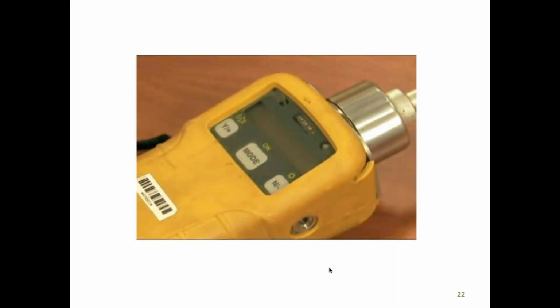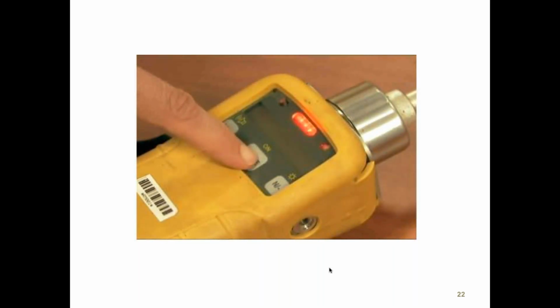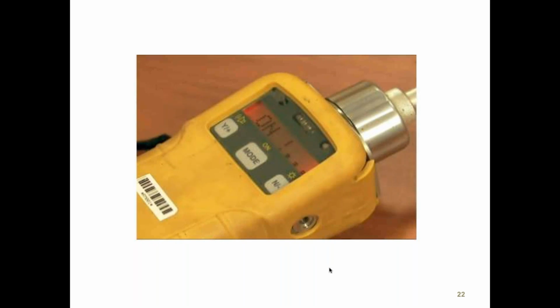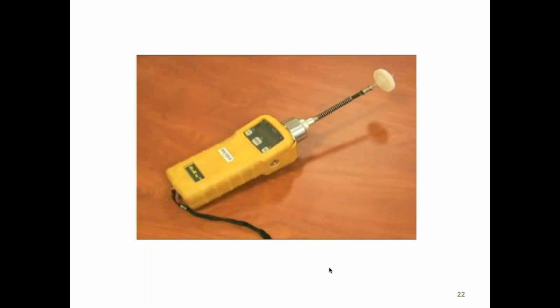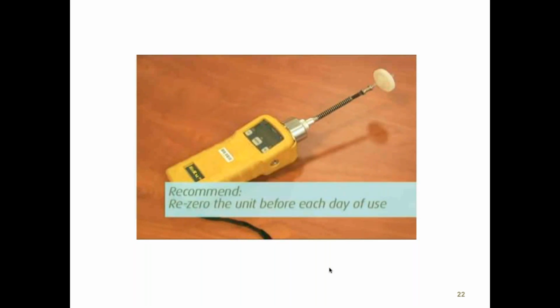One of them is for the charger, and the other one is to allow the unit to connect to a computer. Push the on button. Diagnostics checks. This will take approximately 2 minutes to complete. Once the unit has gone through the diagnostic phase, it will begin to take readings and data log results. Although Galson Laboratories zeroes the unit before it goes out, we recommend that you re-zero the unit before each day of use. If you have a known concentration span gas available, a bump test is also recommended.